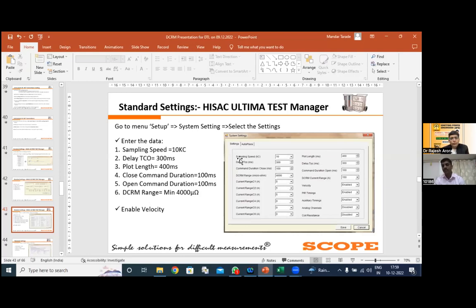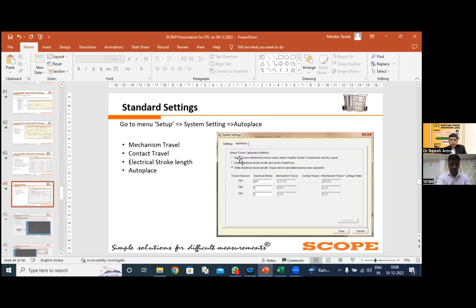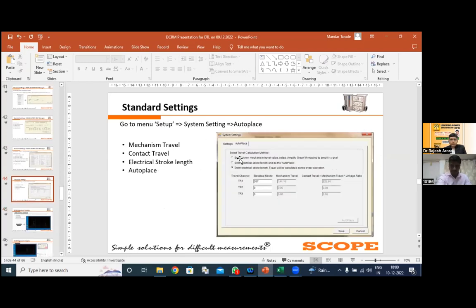Why is it 400 milliseconds? Because we are offering the delay equal to 300 milliseconds. And suppose in case of a spring mechanism or spring pneumatic mechanism, or pneumatic mechanism, your maximum tripping time is around 15 to 30 milliseconds. So in that case, your plot should get enough plot length to capture the entire DCRM signature. Moving ahead, I already told you about the electrical stroke length.